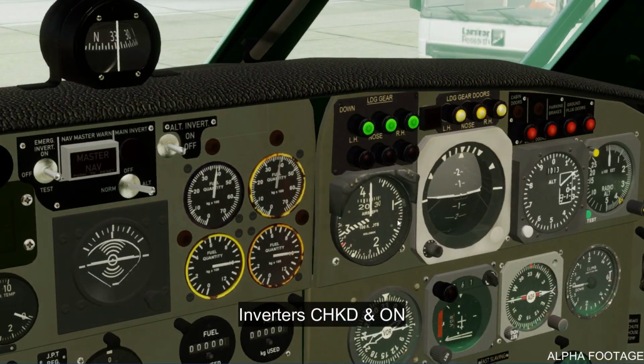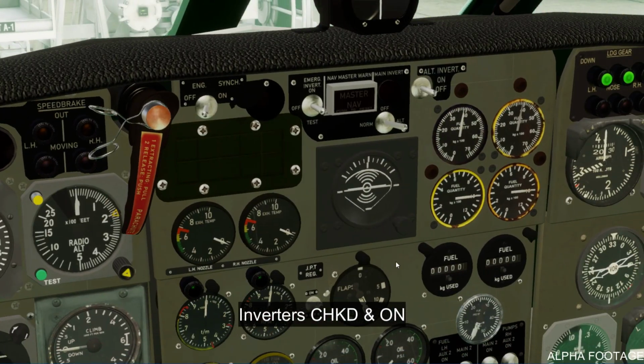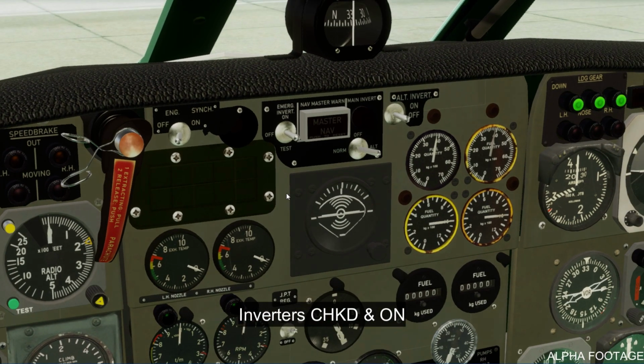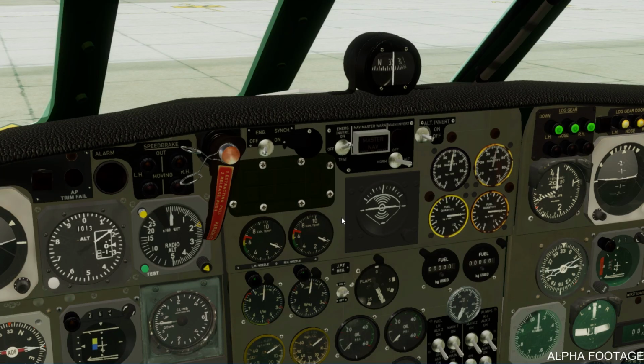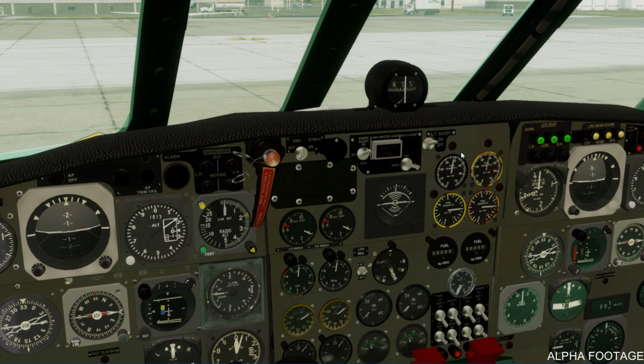Inverters checked on. Okay, place the emergency inverter switch in the position on. Place the main inverter switch in the position alt, it's already there. Place the alternate inverter switch in position on. Check that the red warning light goes out. Voltage is correct, approximately 115 volts phase A and C.